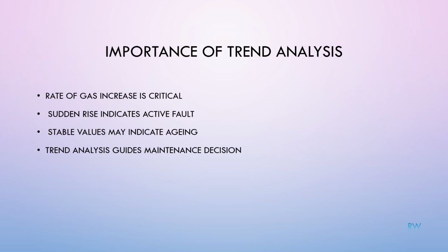Trend analysis is more important than a single reading. A stable gas value may not indicate danger. However, a rapid increase over a short period indicates an active fault. Monitoring gas generation rate is critical for correct decision making.